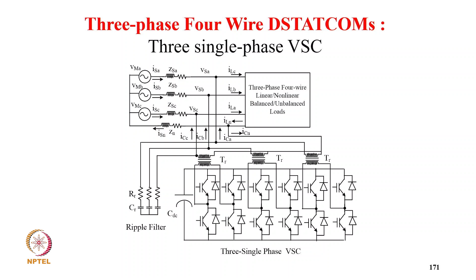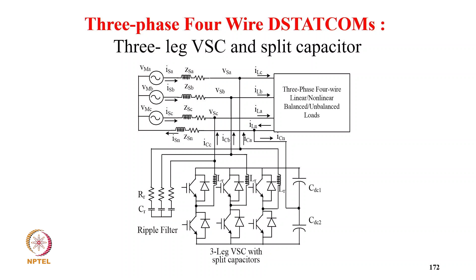And this is 3 single phase with isolation. Here again the H-bridge is used, and that's really quite good in the sense that you can have unipolar switching, which gives double the pulse frequency, and the size of the filter can be reduced. Like this, a 3-phase bridge with neutral uses the midpoint of the capacitor for neutral current compensation.